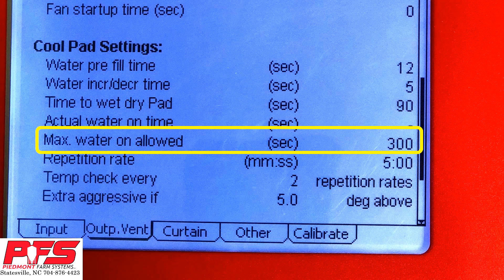Max Water On Allowed. If you don't want your Cool Pad to run continuously, then the Max Water On Allowed needs to be set so that it is less than the repetition rate time. This is where a lot of people run into issues with their Cool Pad running continuously. This is something to definitely look out for.